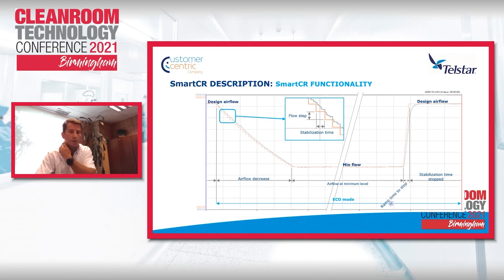Then we have the minimum flow, which is from a safety point of view, when we see that we don't have perturbances and everything is stabilized and balanced. When we did this, in some cases we found that we could go for a lower minimum flow, but there were occasionally some perturbances, so we decided, in safety mode, to fix a minimum flow a bit higher than the one we can reach. We can always reach a lower minimum flow, but we set one that gives us enough assurance of safety for GMP purposes. And then we have the ramp time. This is also a parameter of time, which we fix in a practical situation, where we reduce the time as much as possible, but minding that the pressures are not unstable for a long time.